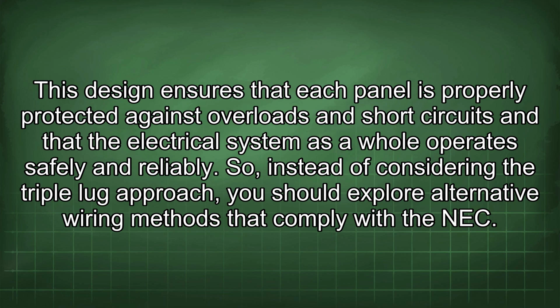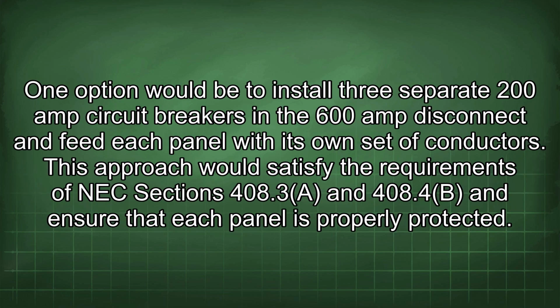So, instead of considering the triple lug approach, you should explore alternative wiring methods that comply with the NEC. One option would be to install 3 separate 200 amp circuit breakers in the 600 amp disconnect and feed each panel with its own set of conductors. This approach would satisfy the requirements of NEC Sections 408.3(A) and 408.4(B) and ensure that each panel is properly protected.